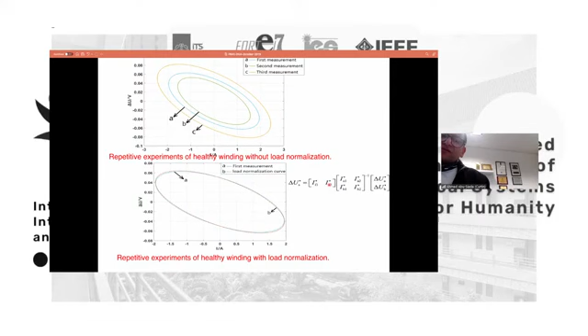I'll stop here with a simple comparison of what I presented today. The current industry practice uses the frequency response analyzer, an offline technique that is accurate, but has two problems. First, it's offline, so you must take the transformer out of service, and it's not very accurate at low fault levels.